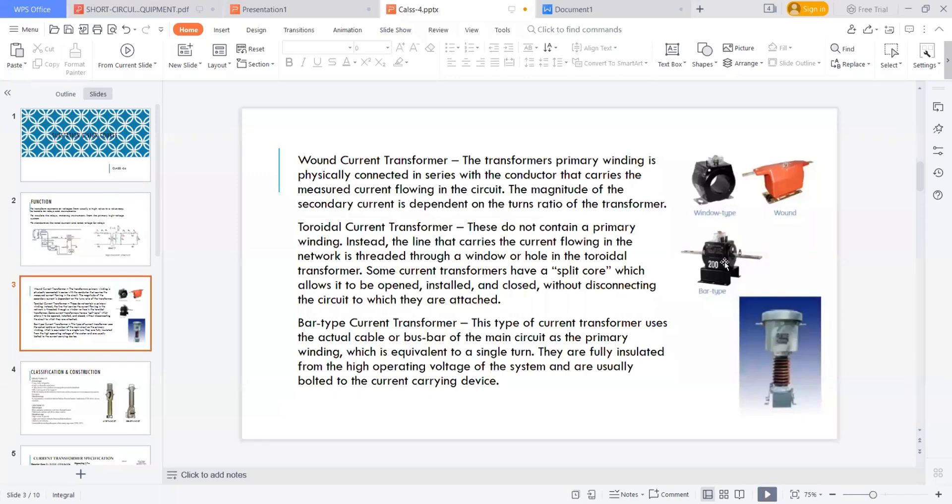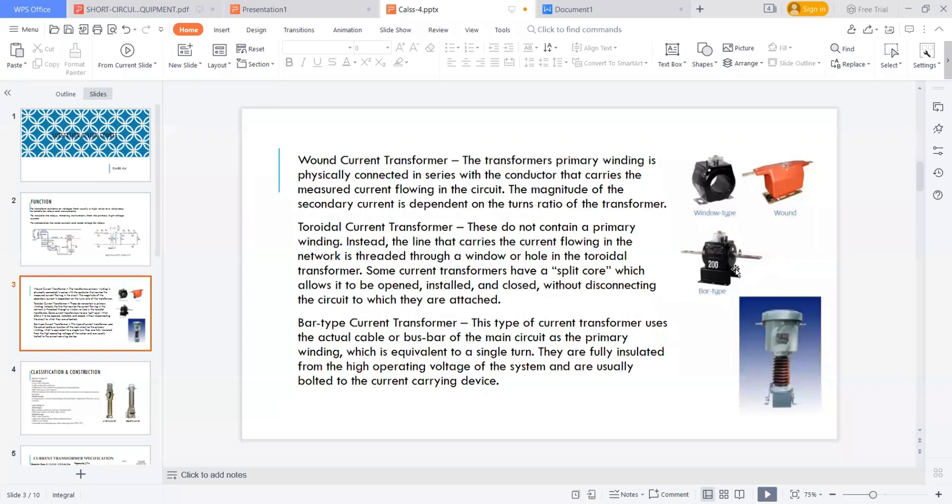And bar type transformer, it is similar to the wound type transformer. Similarly, this type of current transformer uses the actual cable or bus bars of main circuit as a primary winding, which is equivalent to single turn, only a single turn. They are fully insulated from high operating voltage of system and usually bolted to a current carrying device.